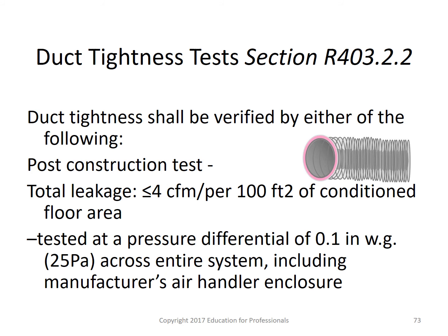And in general, duct tightness tests are performed, and they should be verified by the following: a post-construction test with the total leakage parameters given here, and basically all register boots taped or otherwise sealed. And second would be, of course, the first test you would have done, the rough-in test, giving the leakage amounts allowed here.